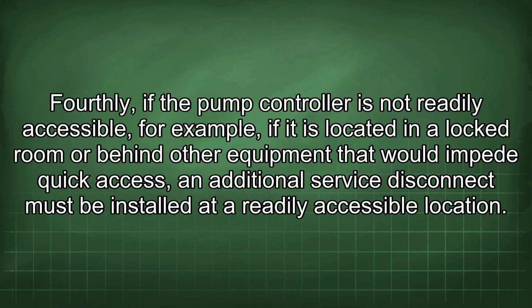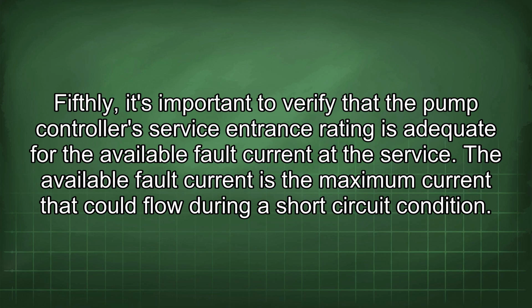Fourthly, if the pump controller is not readily accessible, for example, if it is located in a locked room or behind other equipment that would impede quick access, an additional service disconnect must be installed at a readily accessible location. Fifthly, it's important to verify that the pump controller's service entrance rating is adequate for the available fault current at the service. The available fault current is the maximum current that could flow during a short circuit condition.